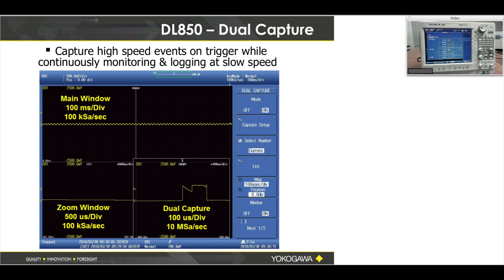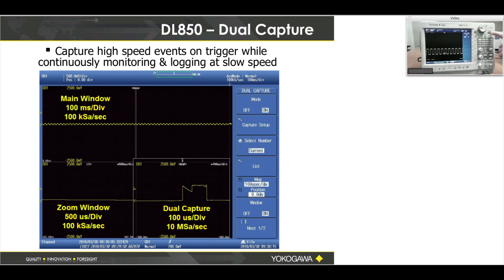Dual capture is something we have not spoken about at all. I'll show you where it's at on the DL850 — press shift and then the acquire button, which is right under the start/stop button. You'll see right under the acquire button it says dual capture. First I want you to understand why dual capture is useful.